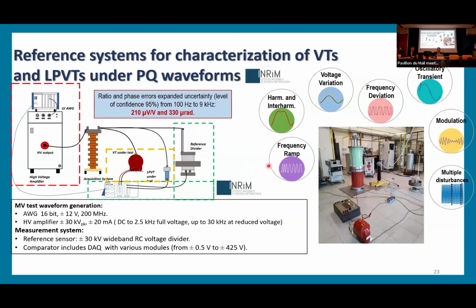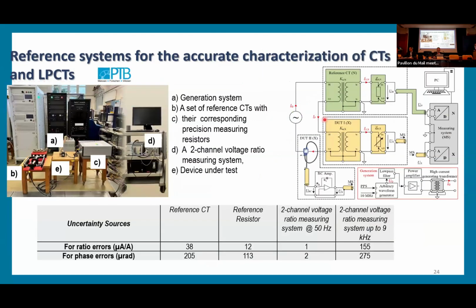Various reference setups were built during this project. I cite just 3 setups, one for voltage transformer characterization at INRIM. It makes use of an arbitrary waveform generator, a medium voltage amplifier up to 30 kilovolt, a reference divider homemade by colleagues of INRIM, a comparator made by a National Instruments data acquisition board ranging from 500 millivolt up to 400 volt input range. And it is able to generate all the cited disturbances up to 9 kilohertz.